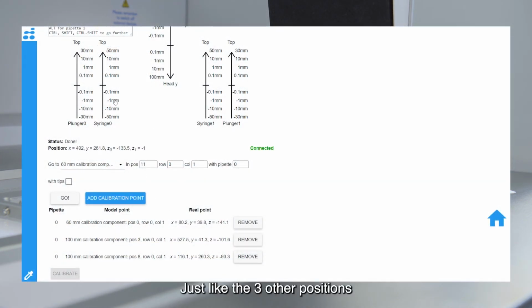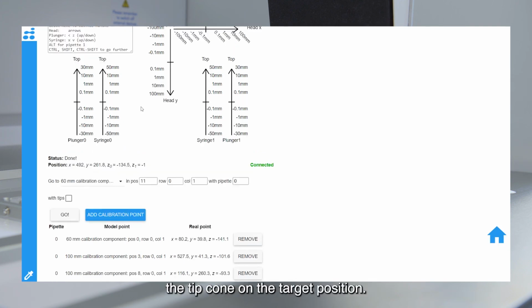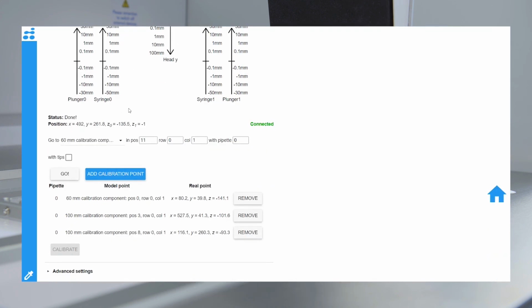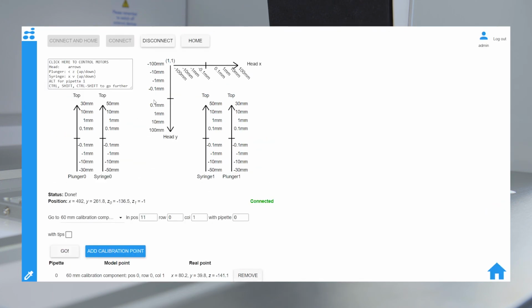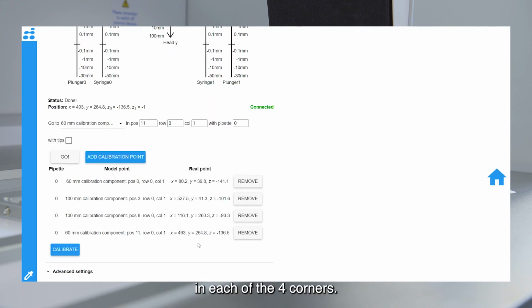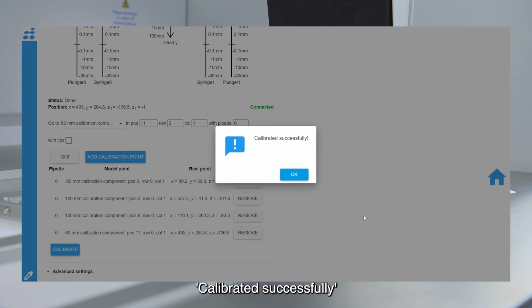Just like the 3 other positions, you use the navigation controls to position the tip cone on the target position. In this case, you lower it approximately 5 millimeter. If it needs to be adjusted on the X and Y axis, you need to do that as well. Once you're happy with the target position, you add the calibration point, and now you have 4 calibration points in each of the 4 corners. You can now press calibrate and it will give you a pop-up that says calibrated successfully.